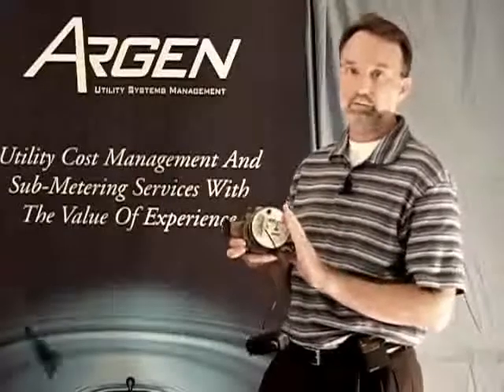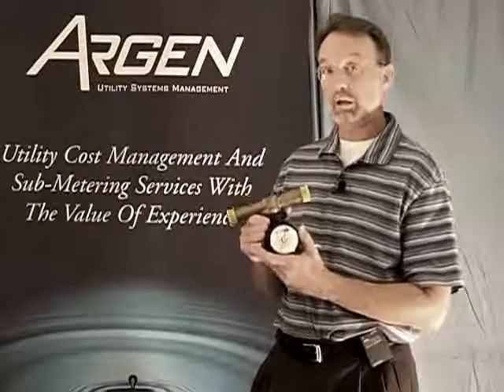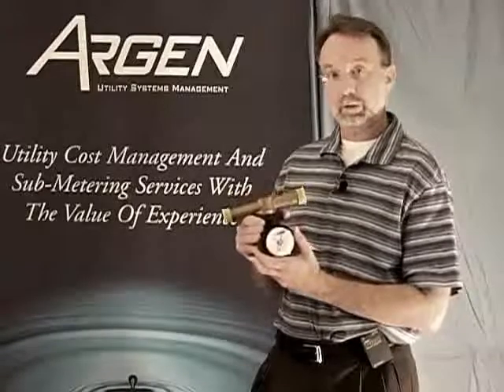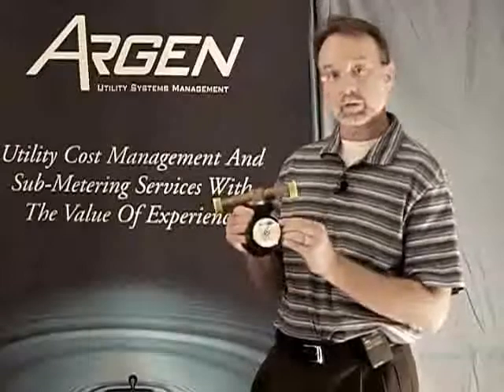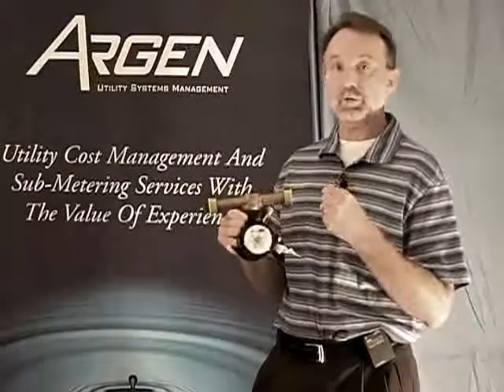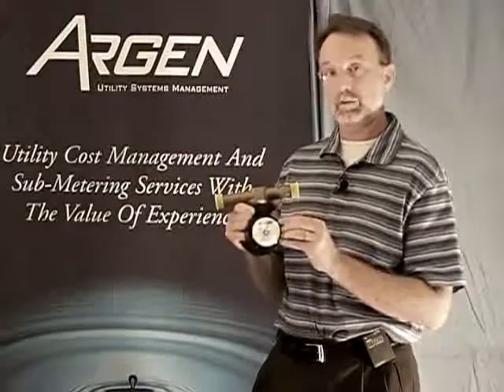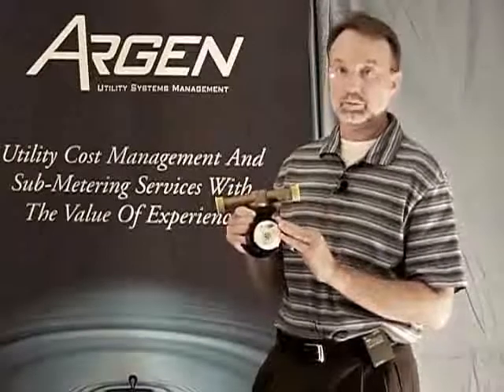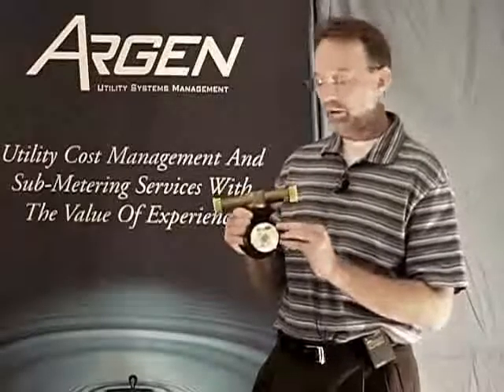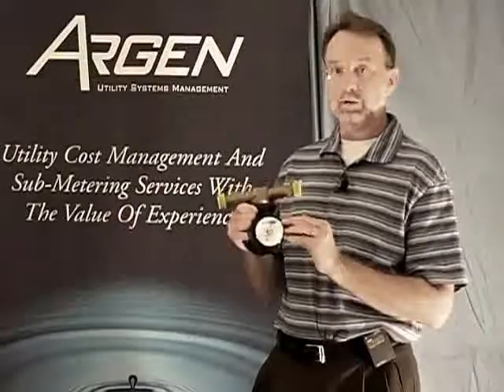In more recent years, we have seen the introduction of wireless radio technology into meter reading systems. In this scenario, a radio transmitter is actually built into the register head of the meter. There are other types of systems that have the transmitter hardwired separately from the meter itself. In this scenario, the power source is a long-life lithium battery that's built into the transmitter. In what is commonly called a drive-around system, the meter reader drives around the site with a radio collector that automatically collects the meter reads.